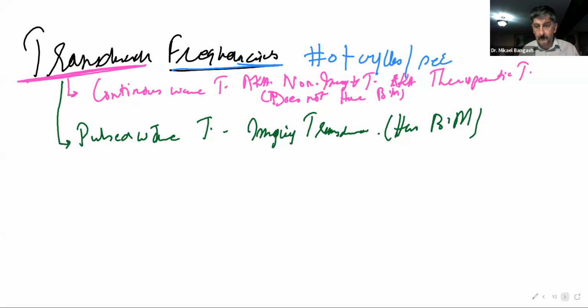Now, as far as a continuous wave transducer is concerned, which we also call a non-imaging transducer, which we also call a therapeutic transducer, we just established that it doesn't have backing material. Clear? And what was it that we said about backing materials? We also called it damping material. So a continuous wave transducer does not have any damping.